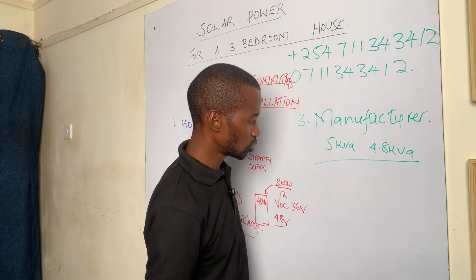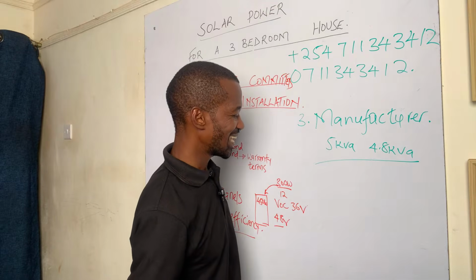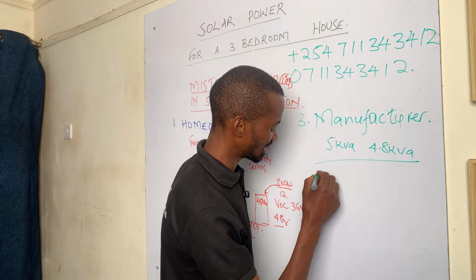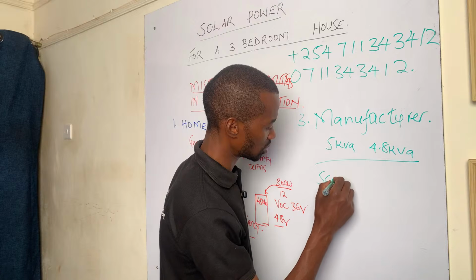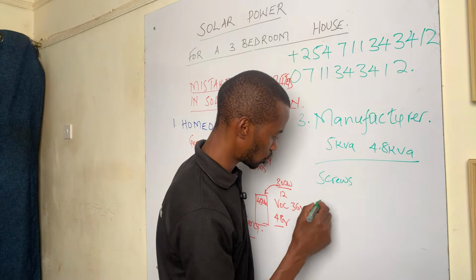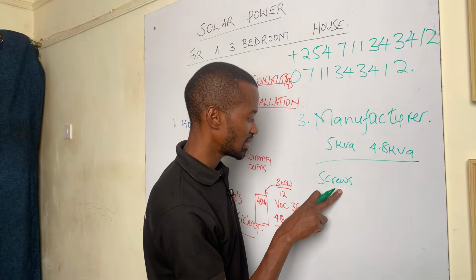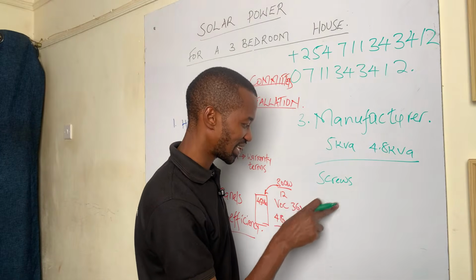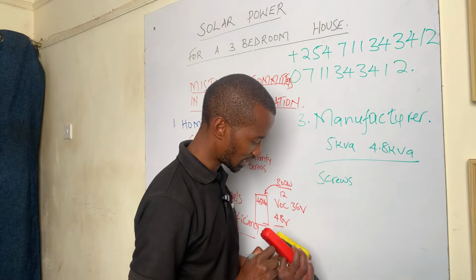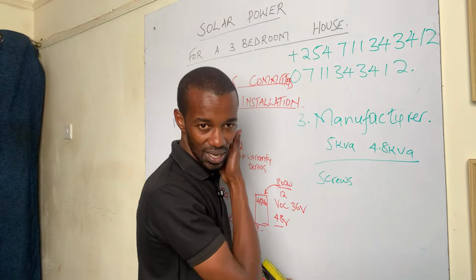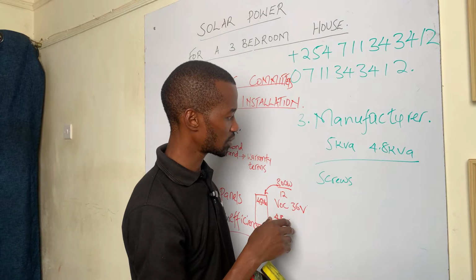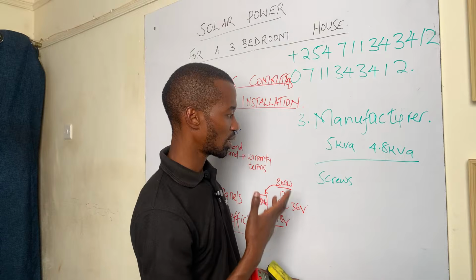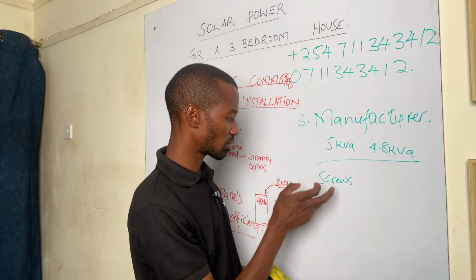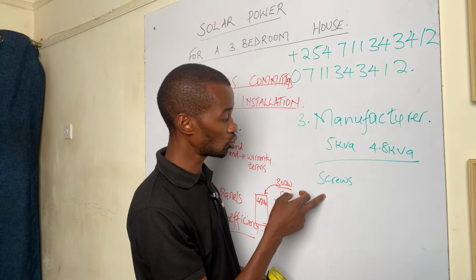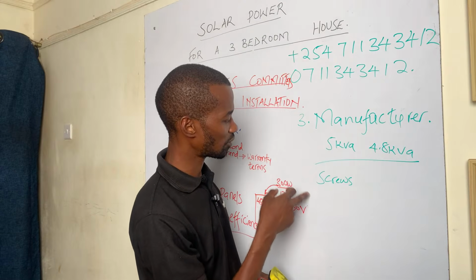Another important thing to note is that upon tightening the screws, this is where the majority of solar power issues happen. Upon tightening, they get to a point where they start sliding. You try to tighten and it slides, and the electrician gets confused about what to do. That is a heavy mistake, especially from the manufacturer's side.